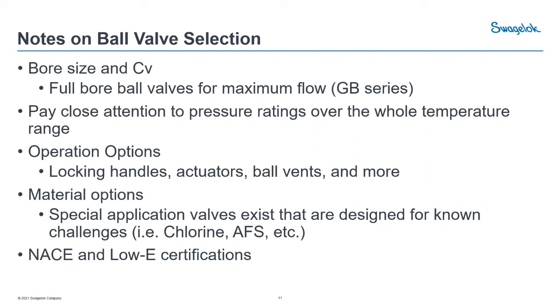Pay close attention to pressure ratings over your entire temperature range. Depending on the seals inside, you can have de-rated pressure containment at higher temperatures. Always look at your operating temperature and maximum temperature to confirm the pressure rating is compatible with what you'll see in your system. Operation options include locking handles for lockout purposes, actuators to automate the ball valve, and different ball vents to depressurize the upstream or downstream side when isolated. Those are all available in our catalog.